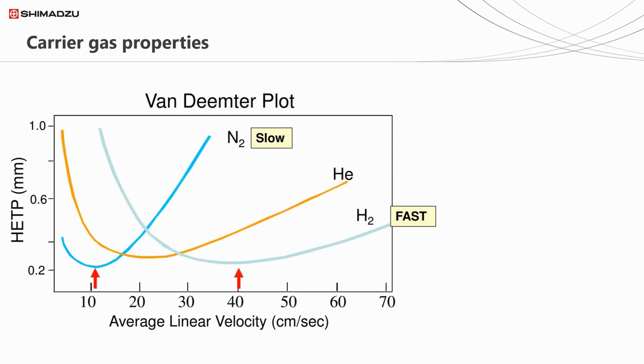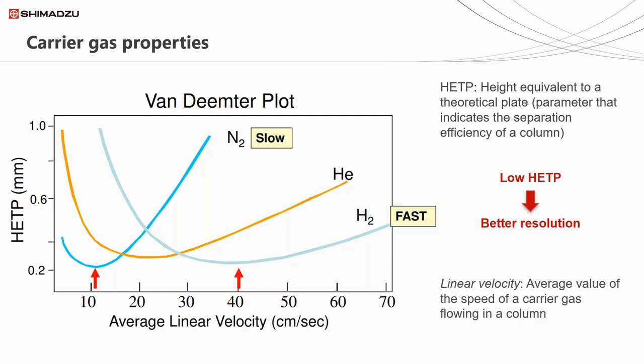The way in which we use a carrier gas and pass it through the GC column is quite complex. There are a variety of gases we can choose, and different speeds and pressures we can pass them through the column. One of the ways to assess this is to look at something called a Van Deemter plot. What we're looking at here is a graph of two properties: the average linear velocity - the speed at which you're pushing your gas through the column - and something called height equivalent to theoretical plates, or HETP. Essentially, it's a measure of separation or resolution, and a lower value of HETP is better, giving us better resolution and more separation between our peaks.